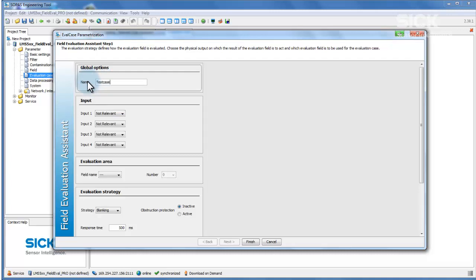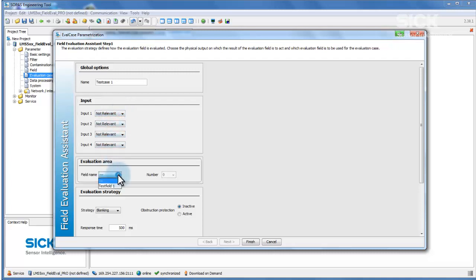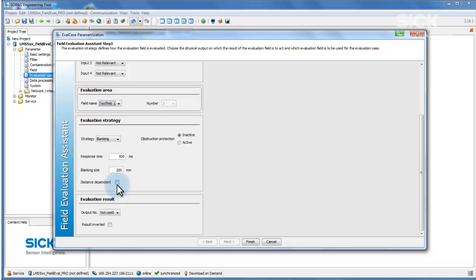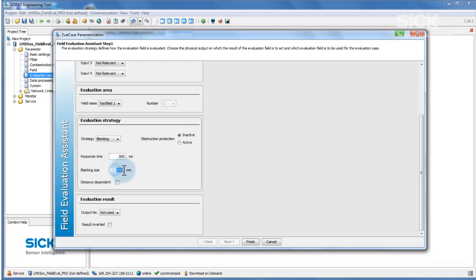Next, select the input combination for which this evaluation case is to be active. A field for which the evaluation case is active must also be selected, along with an evaluation strategy. The evaluation strategy defines how objects are evaluated in the field. It also includes the minimum size an object must be in order to trigger field violation, along with the evaluation time defining how long an object must be in the field before it is violated.